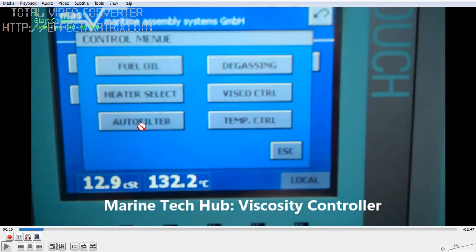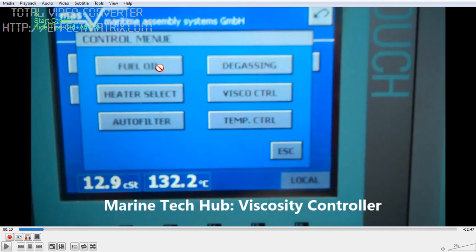Then you have the auto filter, which is backflushing every 2 hours. Then you have the heater — in this case we have steam heating. If both the steam boilers are not working, you can use the electric heater. Then this is the fuel oil: you have HFO and LSMGO, which is the gas oil. So whenever you go to a SECA area, you need to change over the fuel to LSMGO. Whenever you change over from HFO to LSMGO, vapor lock can happen, so we have a degassing system so that the vapor lock can be removed.